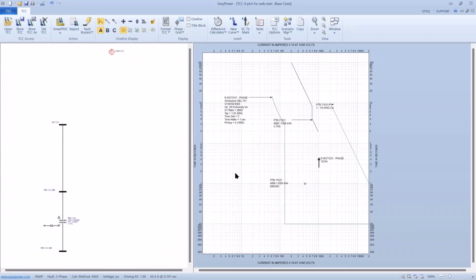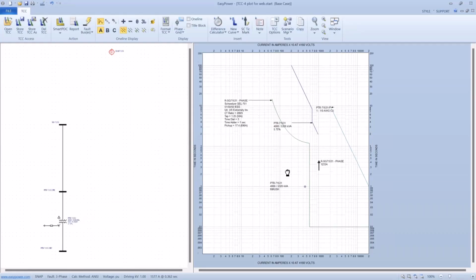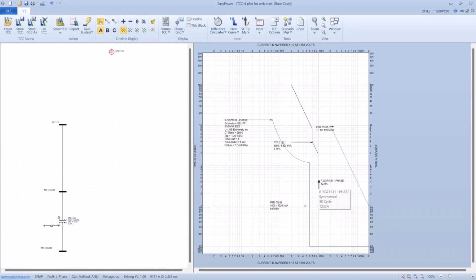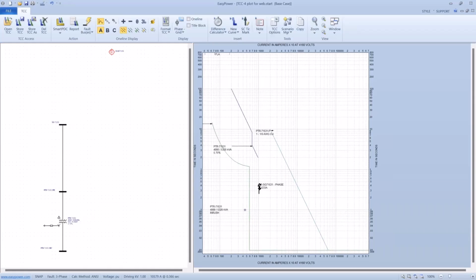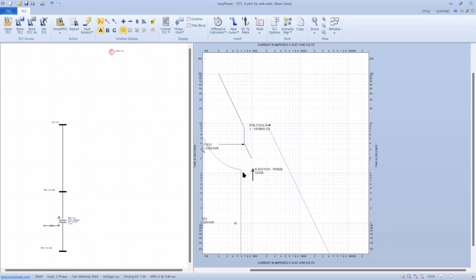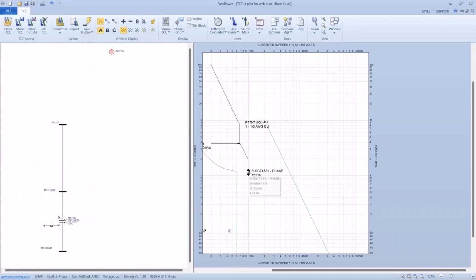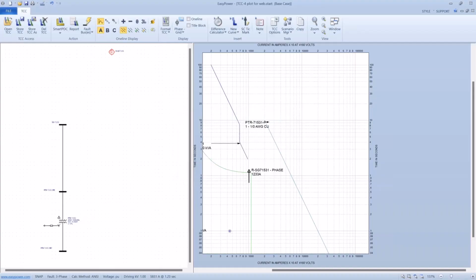And in this case now I don't want to have a trip below the inrush. Here's my symmetrical 30 cycle current, and I want this to be at 1.2 seconds. So 1.2 is going to be up here somewhere. It's 1.16. Looking at the bottom of the screen, 1.2. Now it's not letting me pull this up.